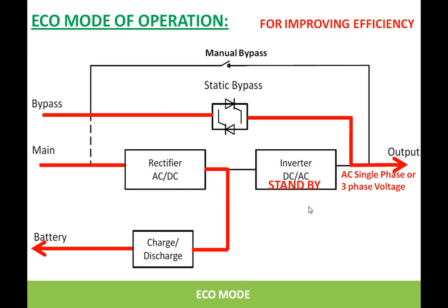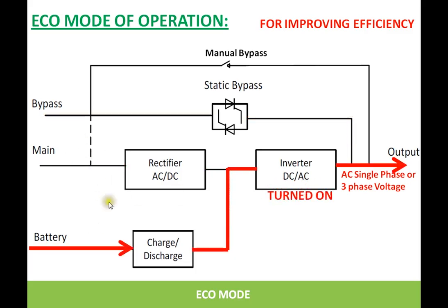When the UPS needs to switch to inverter mode — for example when incoming power fails — the inverter is turned on and the battery bank supplies the required voltage; the inverter converts DC to AC and feeds it to the output. The advantage of this mode is improved overall UPS efficiency. However, one factor must be considered: there is a transfer time involved when switching from static bypass to inverter, in the order of 10 to 15 milliseconds. This must be addressed — if the load can accept this transfer time, you can use this mode; otherwise you should not.